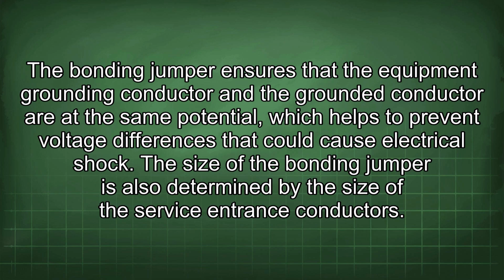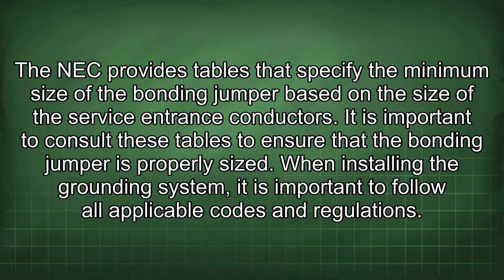The size of the bonding jumper is also determined by the size of the service entrance conductors. The NEC provides tables that specify the minimum size of the bonding jumper based on the size of the service entrance conductors. It is important to consult these tables to ensure that the bonding jumper is properly sized.